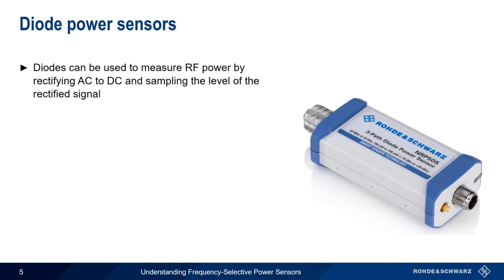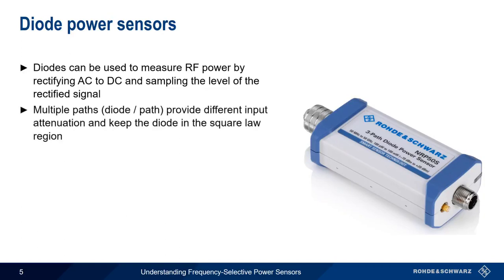Another way that we can measure RF power is by using diodes. Diodes are used to rectify the power — that is, convert AC to DC — and the sensor then samples the level of the rectified signal. Many diode-based power sensors have multiple paths, with one diode per path and different input attenuation per path. Based on the level of the input signal, different measurement paths are chosen to ensure that the diode is operating in its so-called square law region, which ensures accurate results.